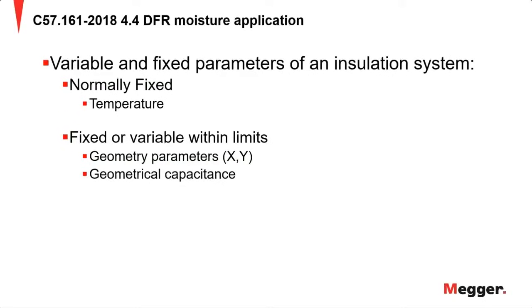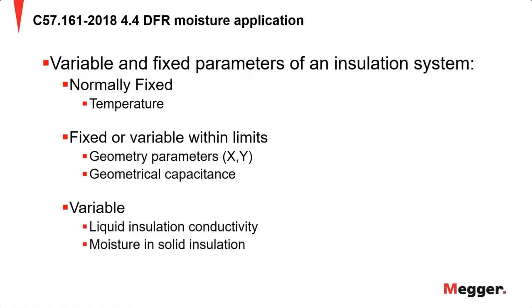So then finally, what we're left with is that the only thing that can change within the system is going to be the liquid insulation conductivity and the moisture in the solid insulation. Because we know that during the test, the temperature of the bushing is not going to change. We know that the capacitance and the XY geometry inside is not going to change over those couple of minutes. So the only thing that could have changed from the previous time is degradation of the insulation, and again, being that liquid or solid insulation.